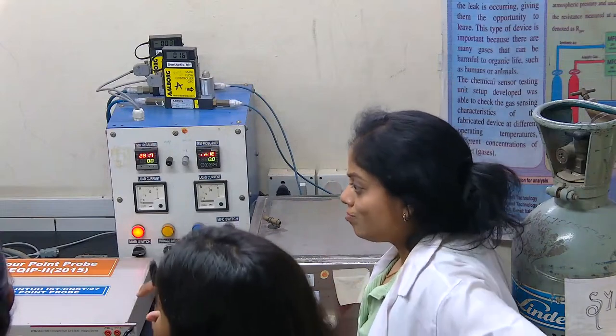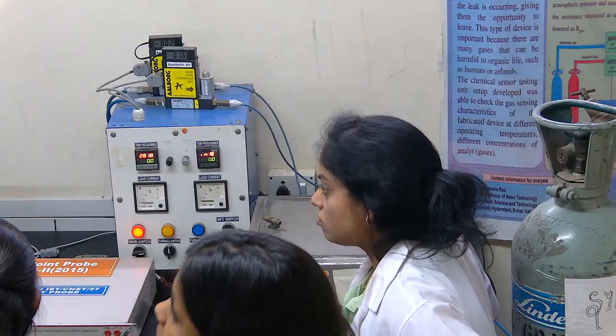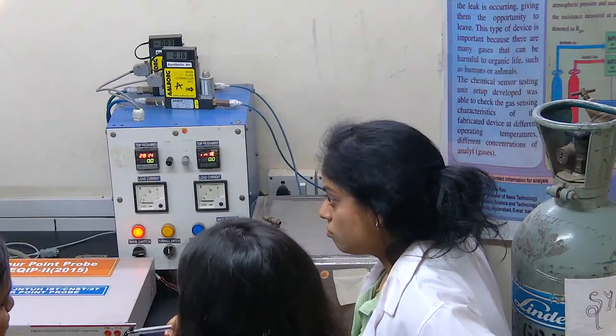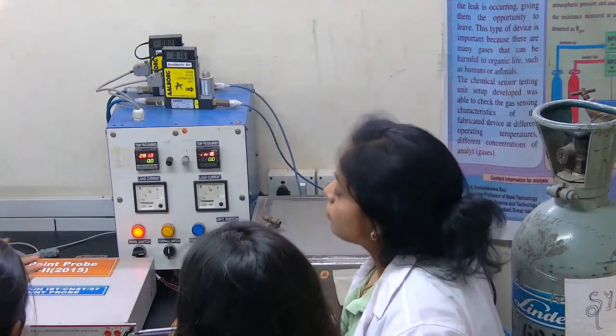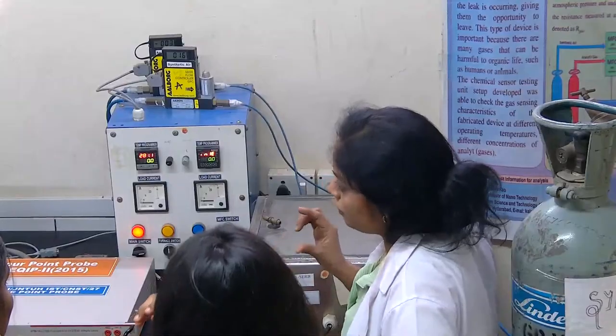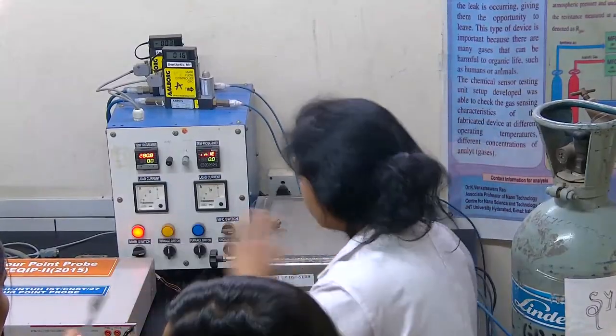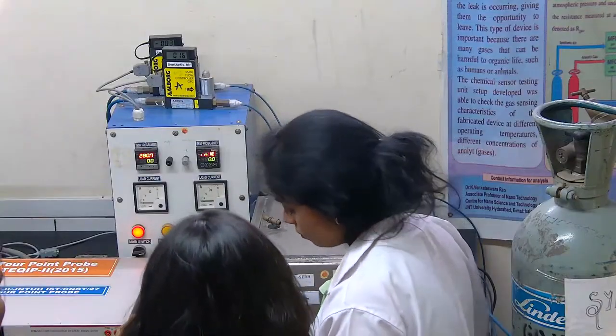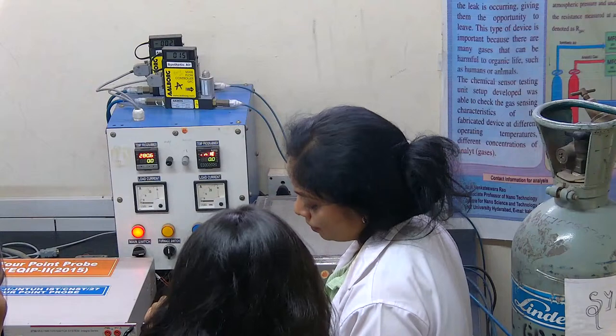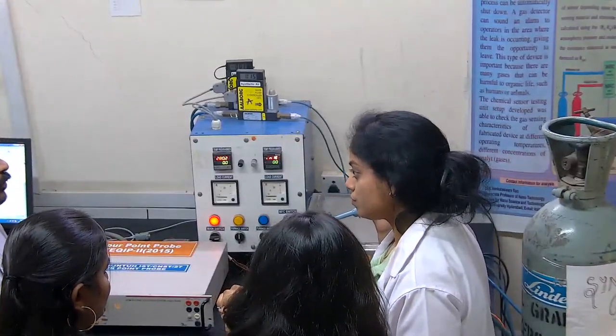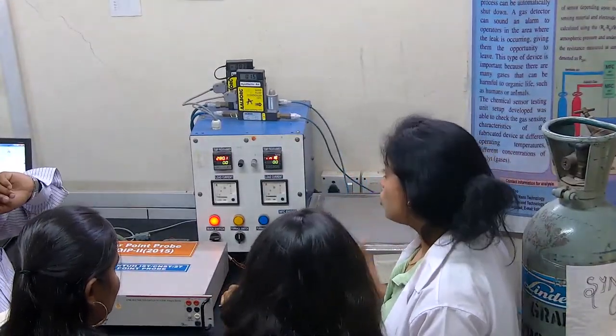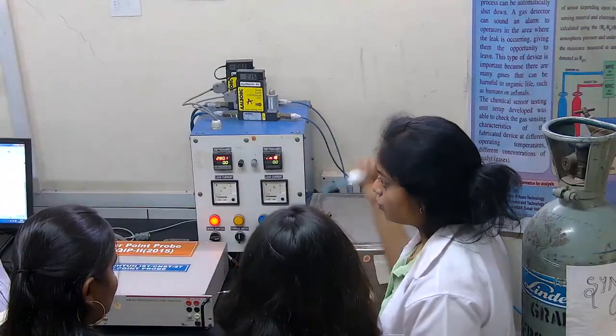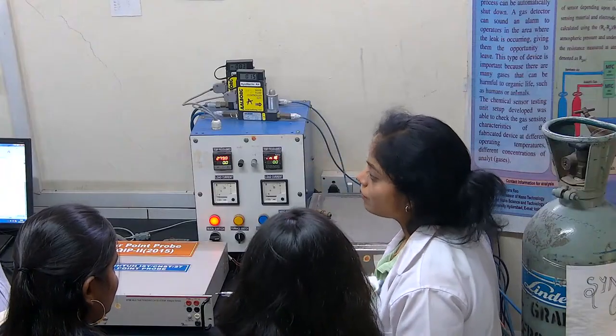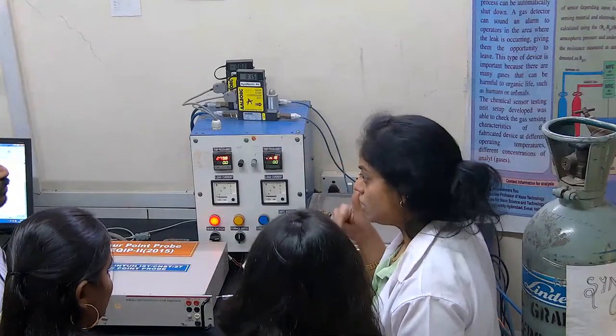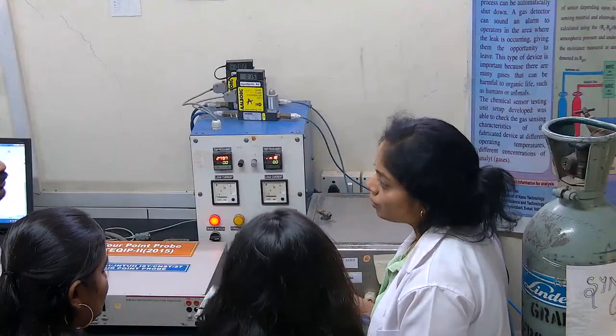But you said after fixing the analyte gas at 15, what is giving a drop to optimize that 15? How do you mix the other interference? 15 ppm should be... We use specific properties. Once the hydrogen is fixed, then we'll go for this. If the hydrogen is 15 ppm, we'll go for 15 ppm over here. We'll suck the respective gas and we'll make it fall over there. The synthetic air will be 85 only. We'll open this, take the hydrogen, make sure it is falling, and run the gas. But advanced instruments are such that they are not just one inlet. Some 10 to 15 inlets are being passed. Then I think there won't be a problem for that.